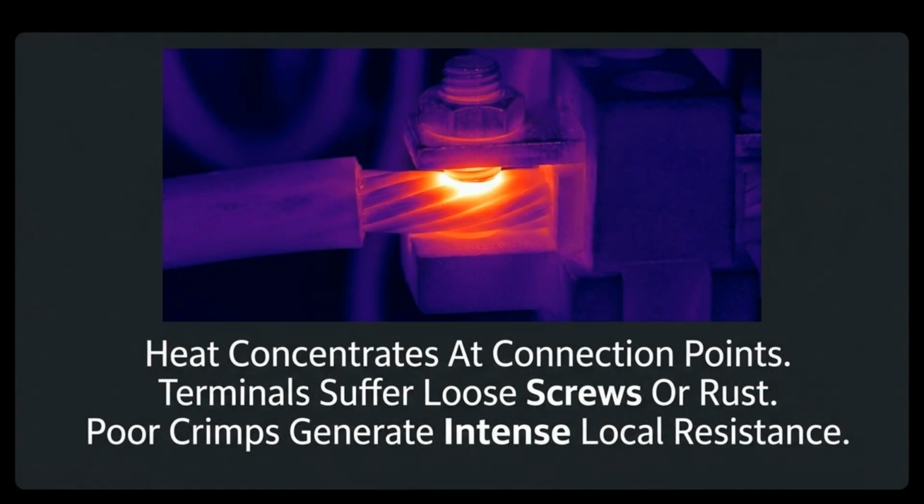Resistance faults concentrate heat at connection points. This intense local resistance is often caused by loose screws, corrosion, or poor crimps at the terminals.